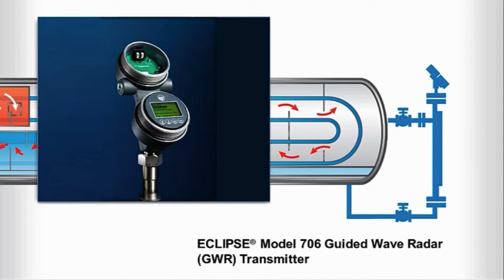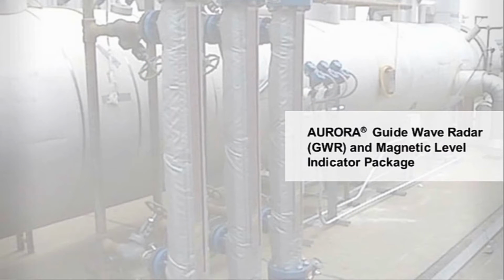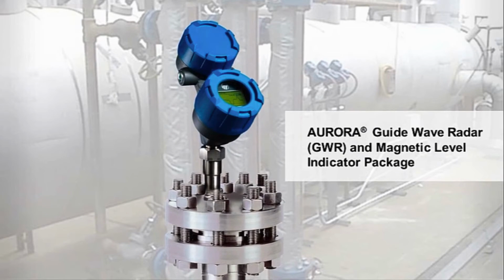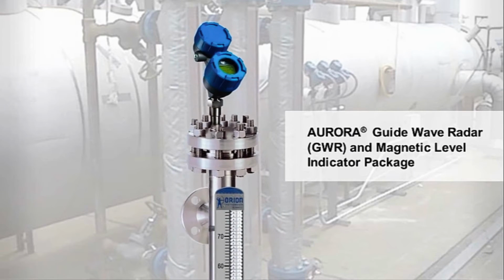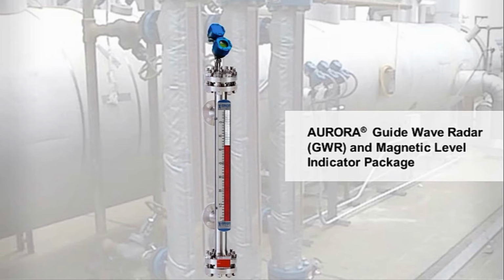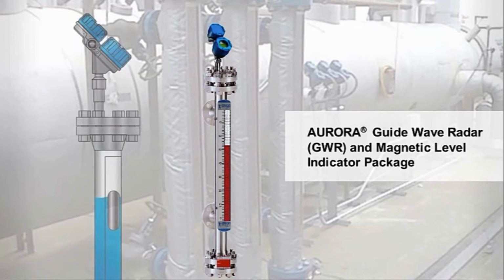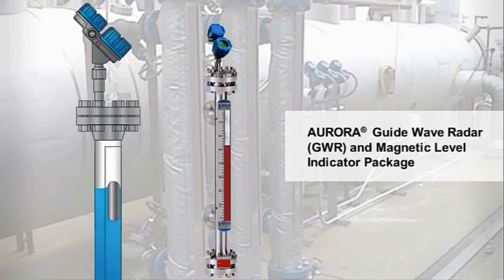The Aurora GWR and Magnetic Level Indicator package merges the operating system of a conventional float-based magnetic level indicator with the leading-edge Eclipse Model 706 guided wave radar transmitter. This allows you to effectively measure low dielectric media, high temperature, and high pressure process conditions and media with shifting specific gravity and dielectric values accurately and repeatedly. The result is a diverse and redundant level measurement solution in a single chamber design.